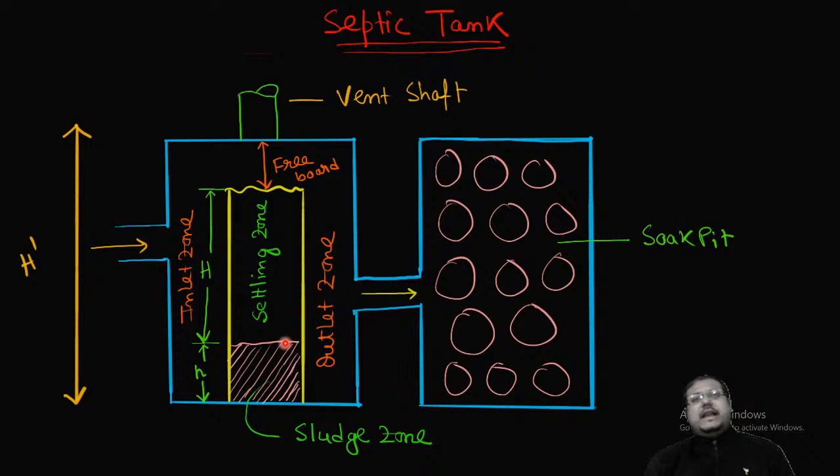लेकिन ये तो मैंने आपको बोला था कि when you are going for any kind of solid digestion or sludge digestion process, it will be essentially anaerobic in nature. तो कुछ भी हो जाए आपका treatment unit, sludge will be digested by anaerobic process. So here in the settling zone, aerobicity or anaerobicity is not the mandatory part, but in the sludge zone, anaerobicity is the mandatory process, correct?